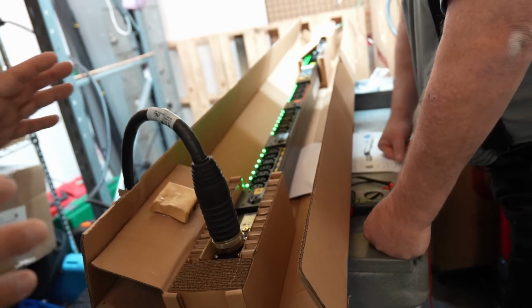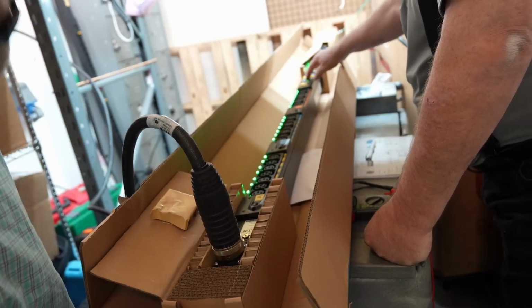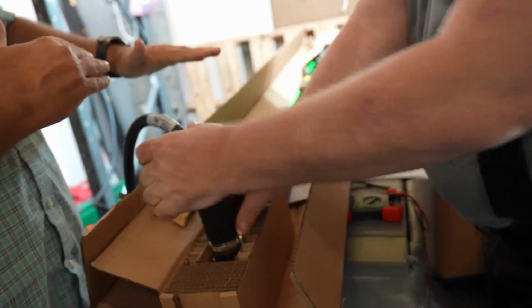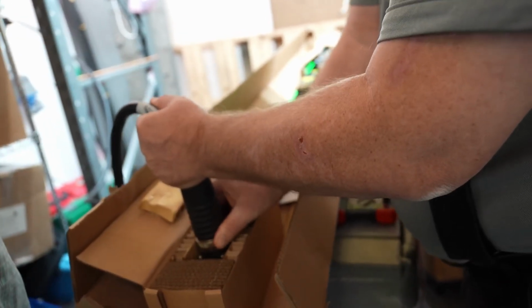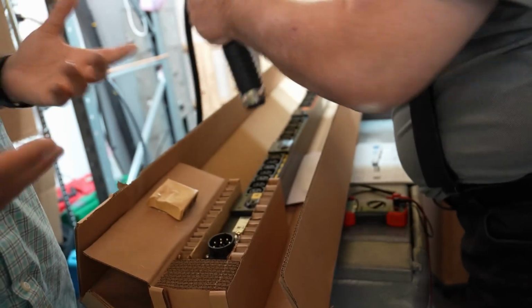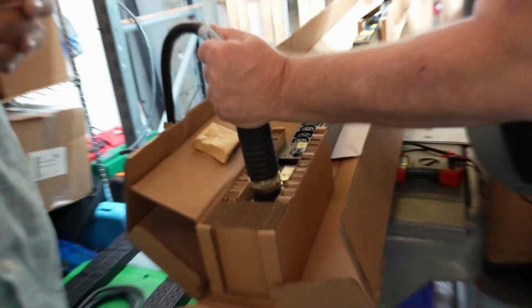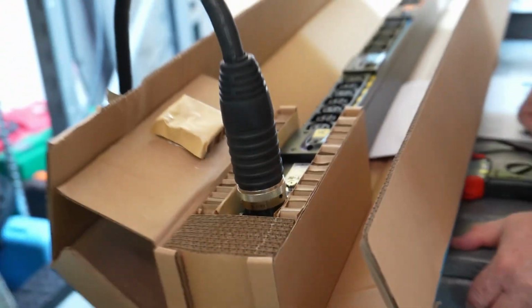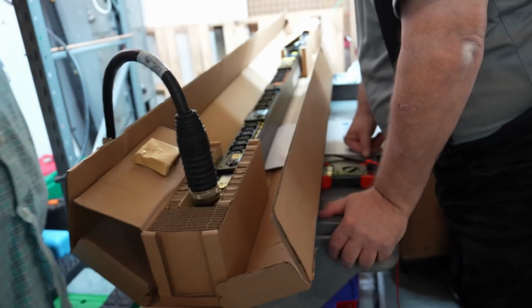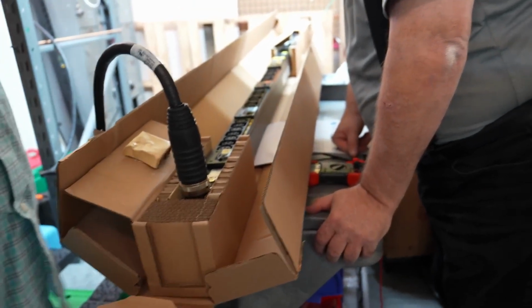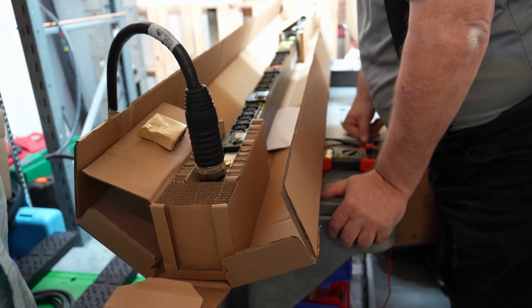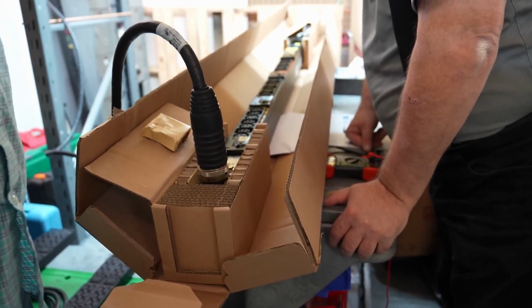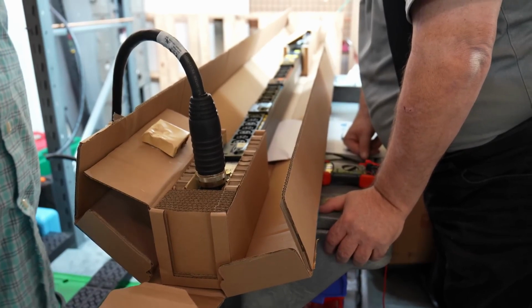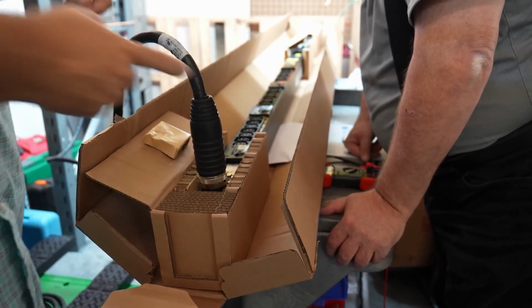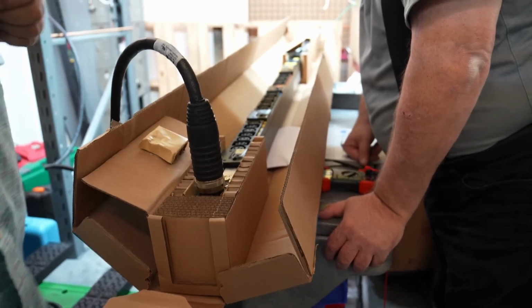The most common scenario we run into is, hey, I started buying services from you 5 years ago when my power needs were this, but now I've grown to the point where I need something more. What does it take to upgrade? Well, it's a two-person job of installing additional power circuits under the floor, then removing one of these things physically while it's live, putting a new one in, migrating all the power plugs, and doing that again. When you have to do that twice on a live environment, it takes a lot of time and is highly stressful. Or, I just change out the cable and you're done.